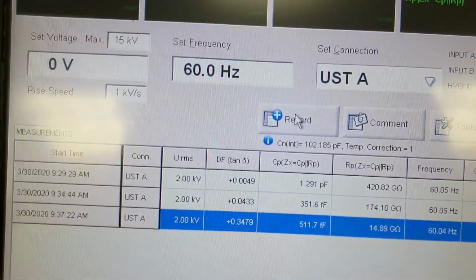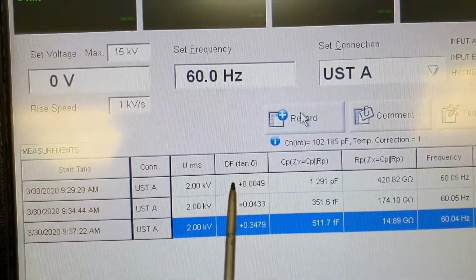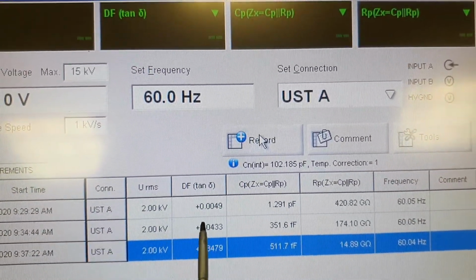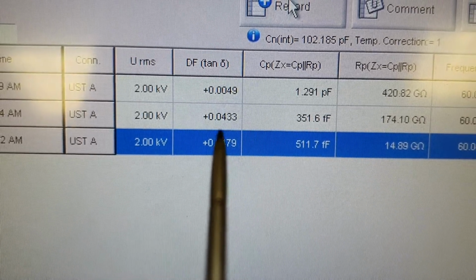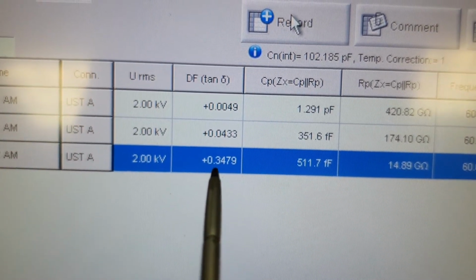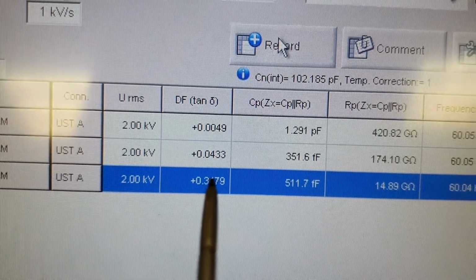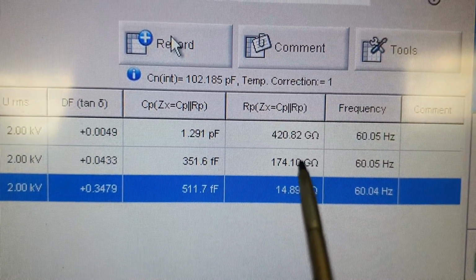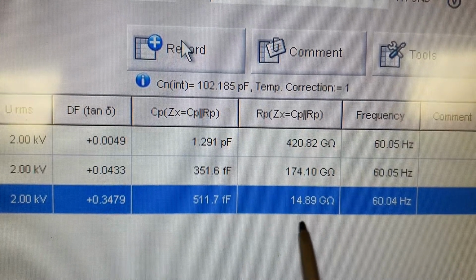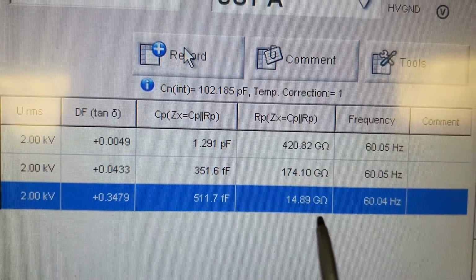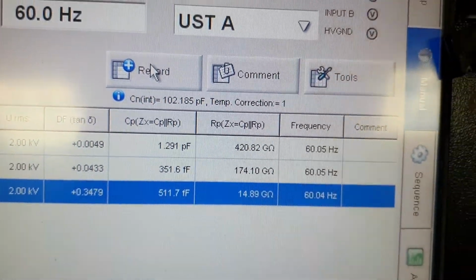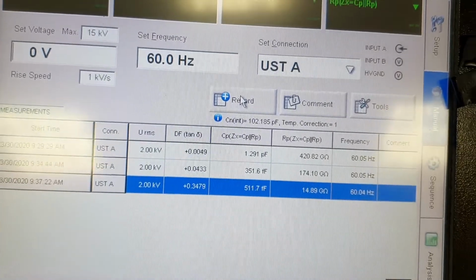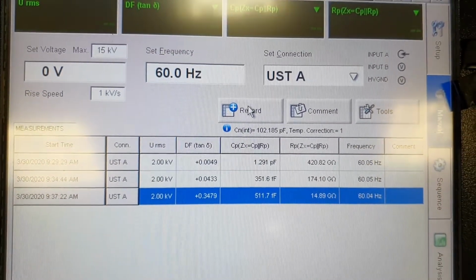So now for the values which we recorded, first was for the insulator, tan delta value, this XLP insulation, then this was the insulator when it was in good condition. Then you can see here the tan delta value has increased for the defective one where we put water, and there is some leakage current, so that is why this value is pretty high. Even the resistance, you can see this was previously 174 for a good insulator and now it decreased to 14.89 giga ohms. So this is how we measure; it can tell you the condition of the insulator based on the resistance and tan delta values.